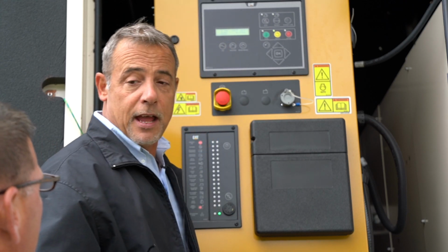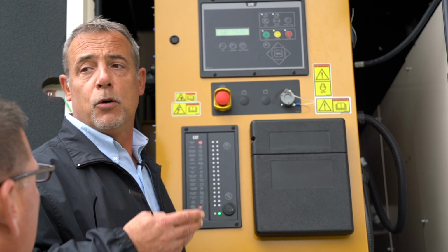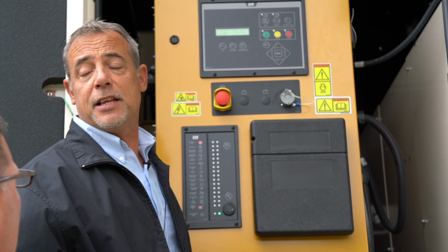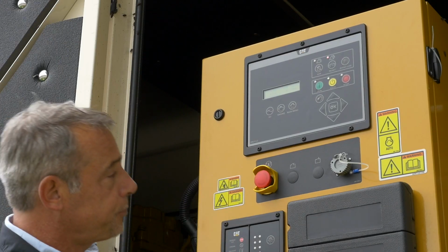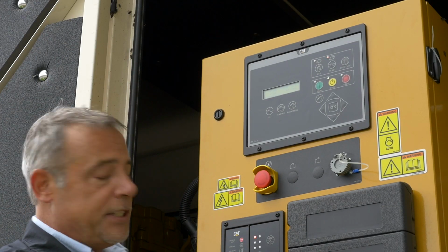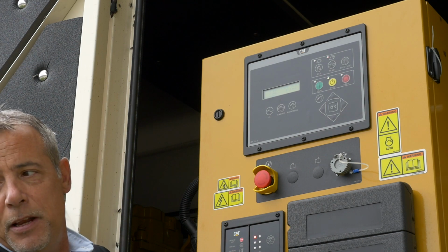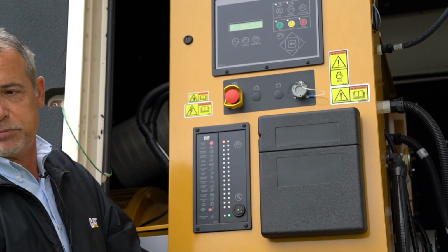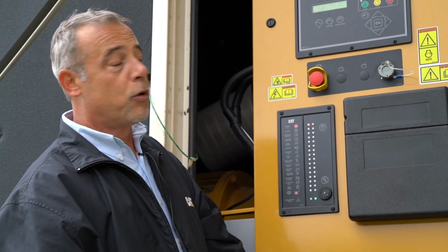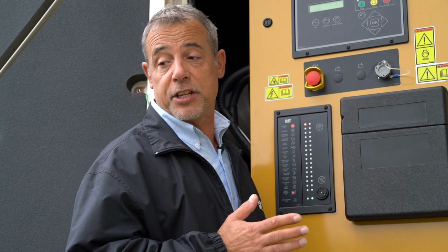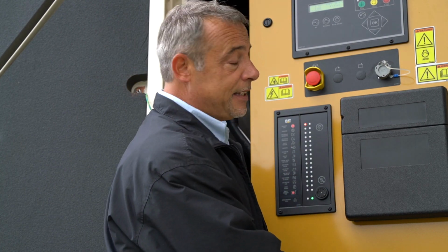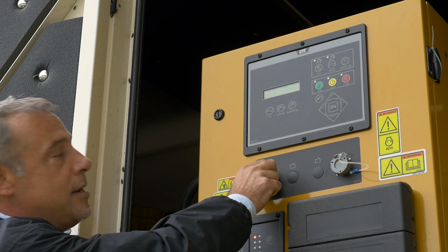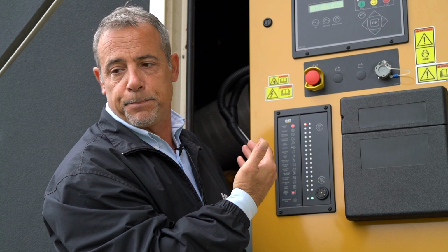All right, let's say you have an alarm ringing, or you're inside, you have a remote annunciator and that's ringing. We're going to cause a fault, and I'm going to show you how to reset these faults. First thing, if you want to silence the alarm, hit the silence button. That'll silence the alarm, but the alarm's still lit that the emergency stop's been pressed in, or you could have a malfunctioning e-stop also. In order to reset that fault, you would come out, check, and make sure all the e-stops are pulled out. You turn them clockwise and let it spring out to you.